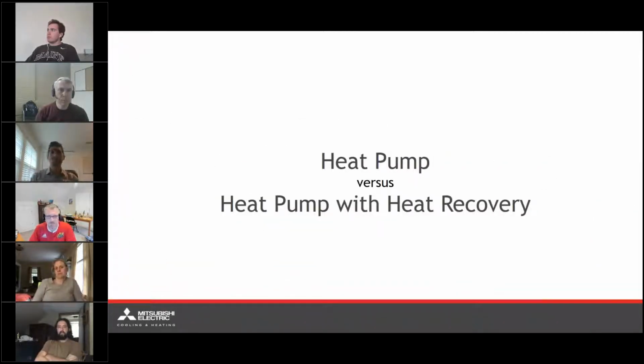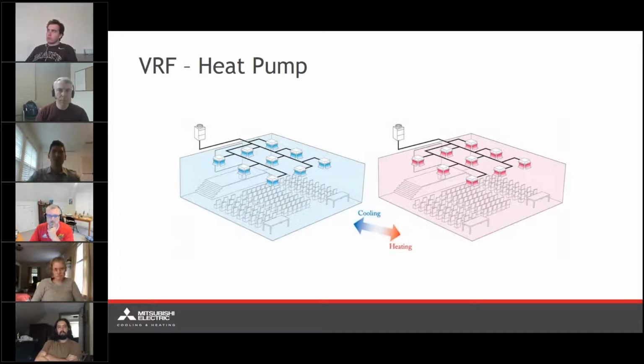All right, so we're just going to start with a quick overview of VRF and the components that make up a VRF system. When we're talking about a VRF system, we're talking about one of two different subfamilies. We have our heat pump family of equipment, which is shown schematically here. We have 9 different fan coils, all attached to one single refrigerant network. And for this particular configuration, all of the fan coils on this one system are going to be in either heating mode or cooling mode. So with this particular system, you're not going to get simultaneous heating and cooling throughout. That's going to require an additional component.